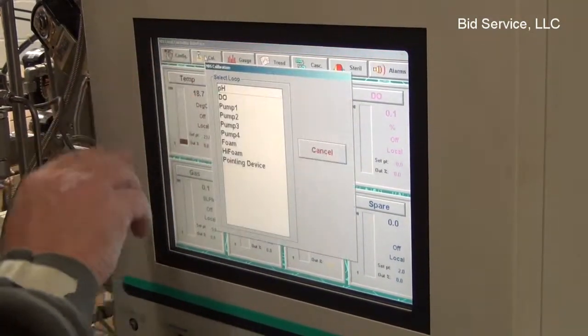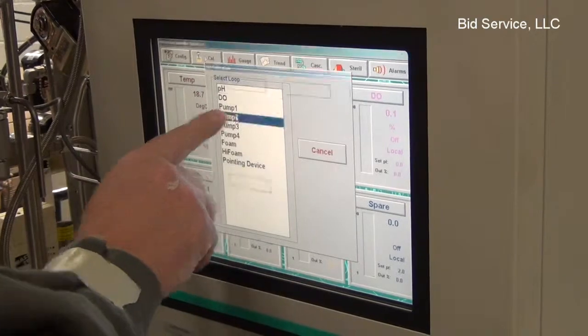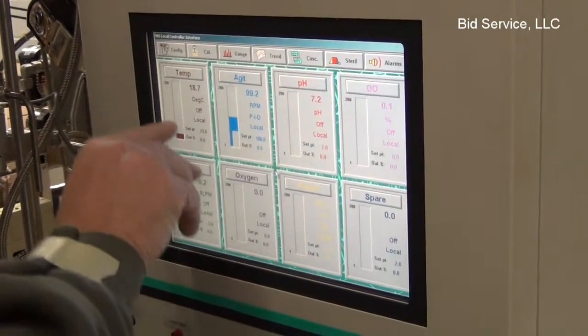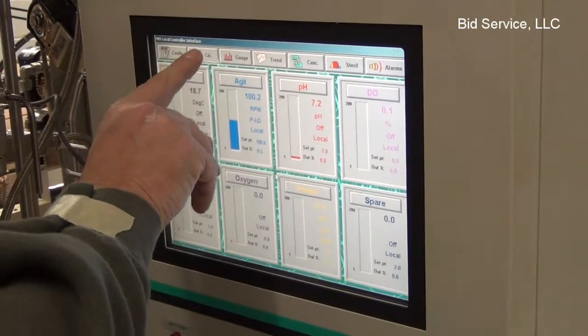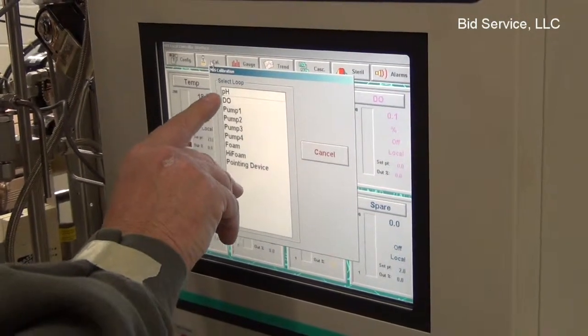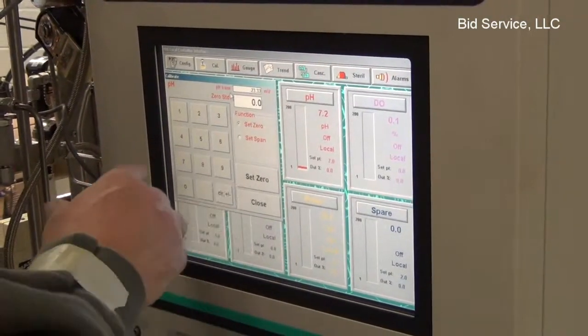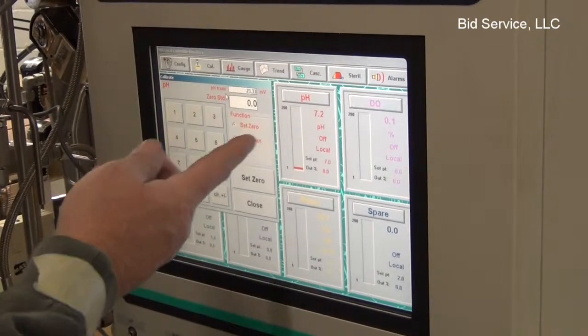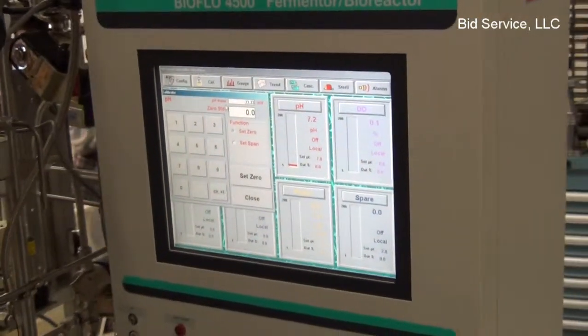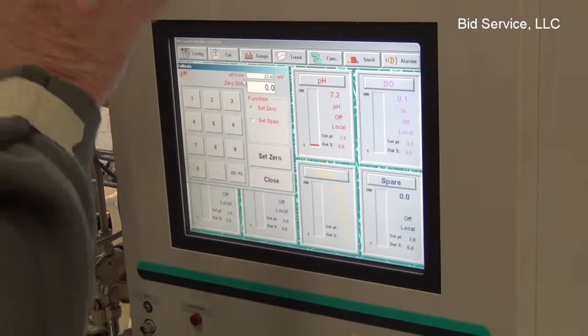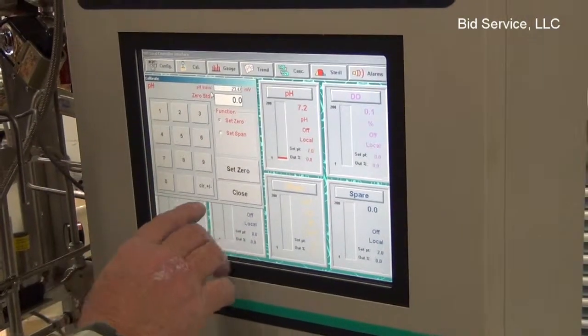Okay. Again, under calibration, you can pick your different things. I picked the wrong one. You can pick something that needs calibration. You can go in there. It tells you what it's set to, what you can set 0, you can set the span. Again, this is dependent upon the module that you're choosing.